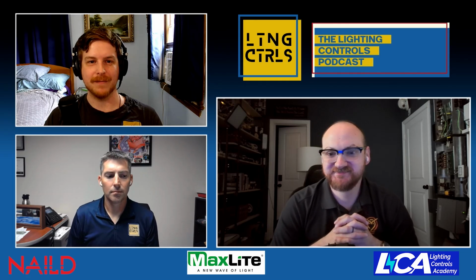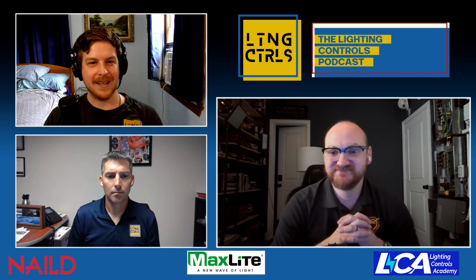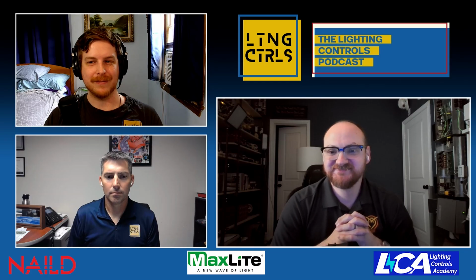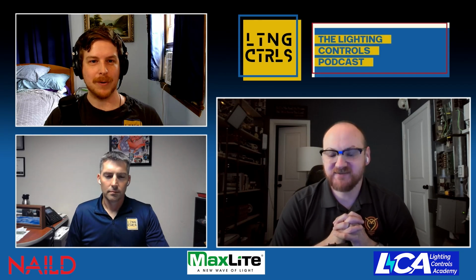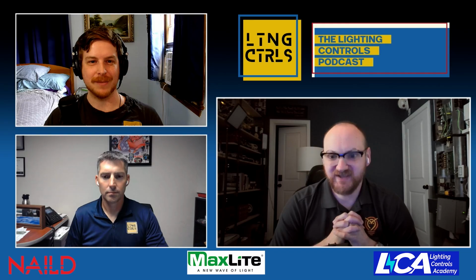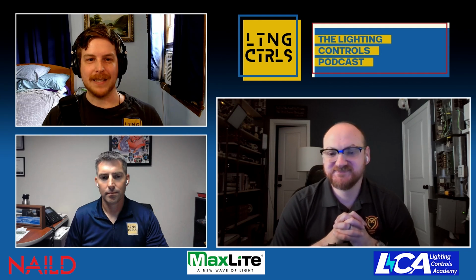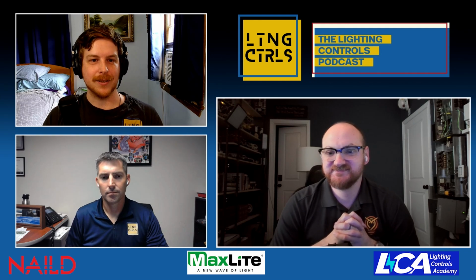I don't know what to tell you, but that's a really good point when we're talking about house lighting in entertainment venues. A lot of people say, well, it can be 0 to 10 volts, it's fine, and it's like, no, it can't. You really should be dimming to off with DMX, which is the shared protocol of the space, because that guarantees integration with both systems, and also gives you the ability to dial into the level you need, which could be like 0.5% to get 1 foot candle, as opposed to the floor of 10% on a 0 to 10 volt line. So yeah, that's something a lot of people might not consider when specing these spaces.